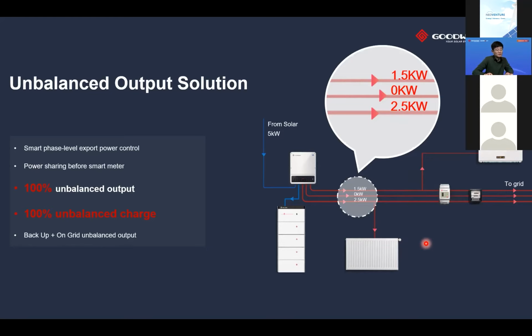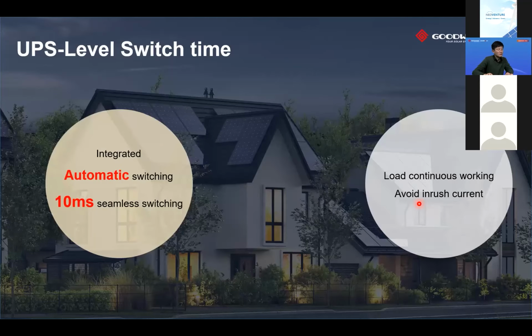For example, in some European countries, they don't allow uploading power to the grid. So three-phase unbalanced output is the only solution for those countries. That is also why our GoodWe storage products are very popular in some European countries like the Czech Republic. And the second one is that we designed the UPS level switch time. Probably I already mentioned it in the last slides. It's less than 10 milliseconds when switching between on-grid and storage power.